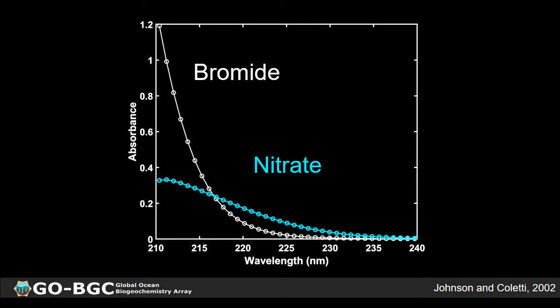and contribute to the overall measured spectra. The dominant signal actually comes from bromide, which is shown here in white. This is the absorbance spectrum for bromide if salinity was about 35. As you can see, bromide absorbs a lot more than nitrate, particularly at wavelengths shorter than about 220 nanometers, so this becomes a dominant signal. On top of that, there's another component that absorbs in the UV, which is dissolved organic carbon, or DOC. We parameterize DOC as just a linear absorbance spectrum that ranges from 210 to 240 nanometers, and this has been shown to be the case in the literature.